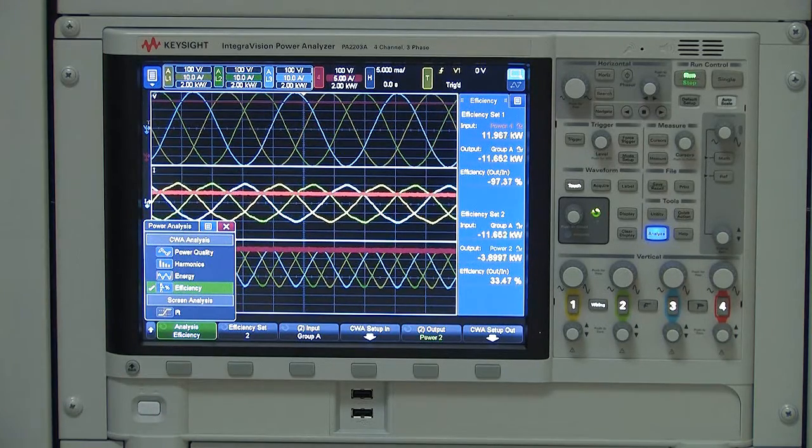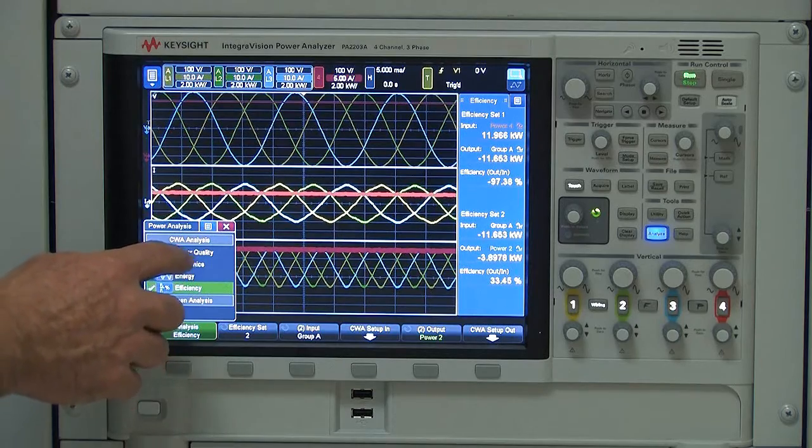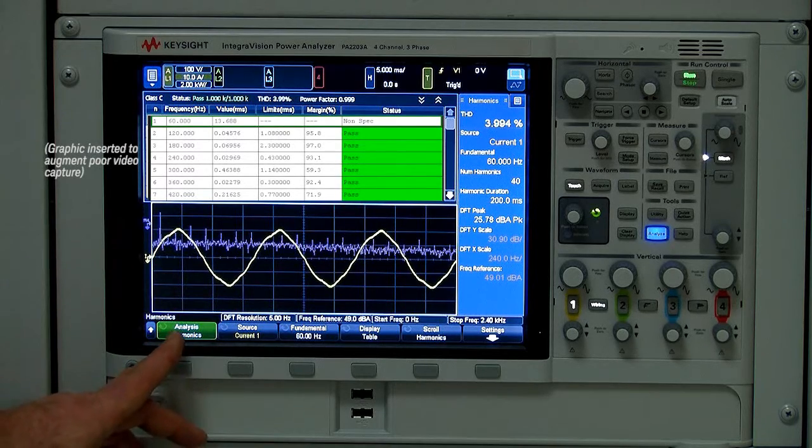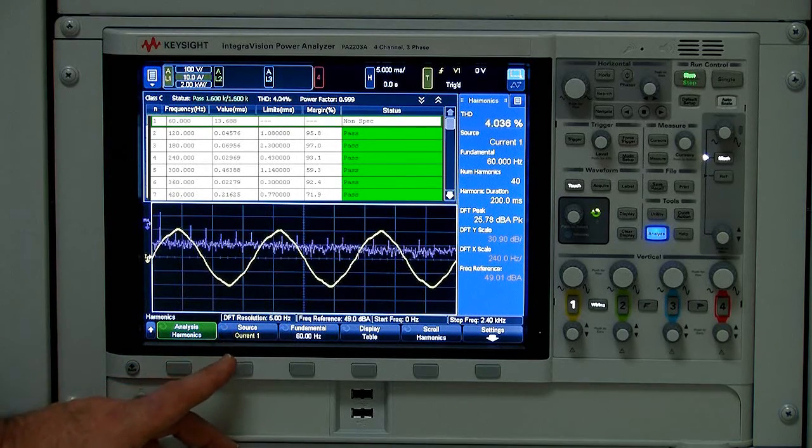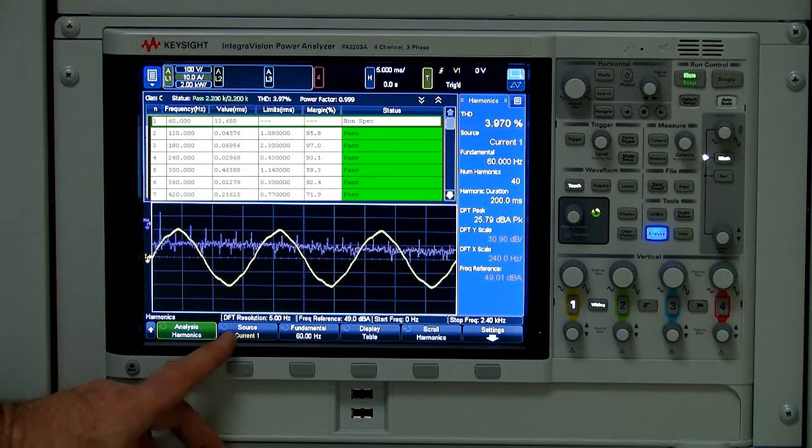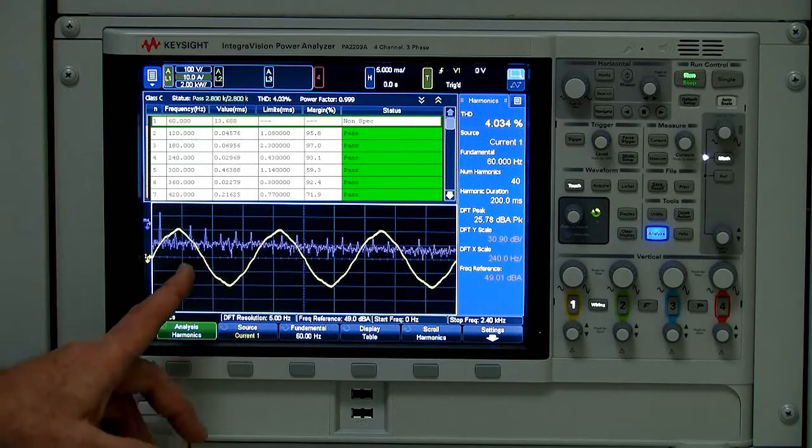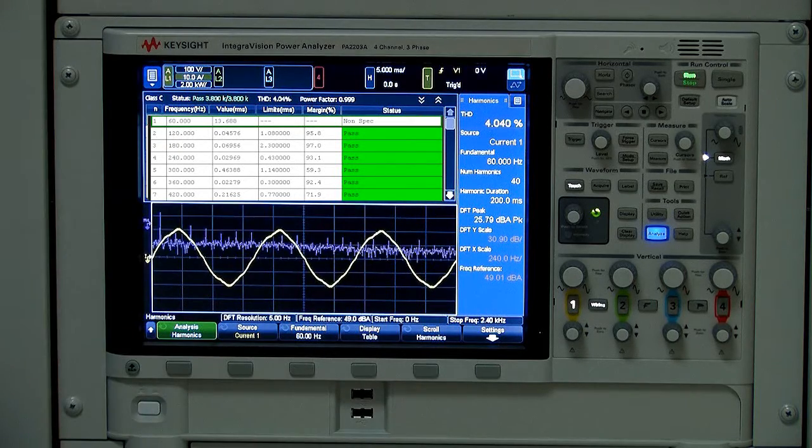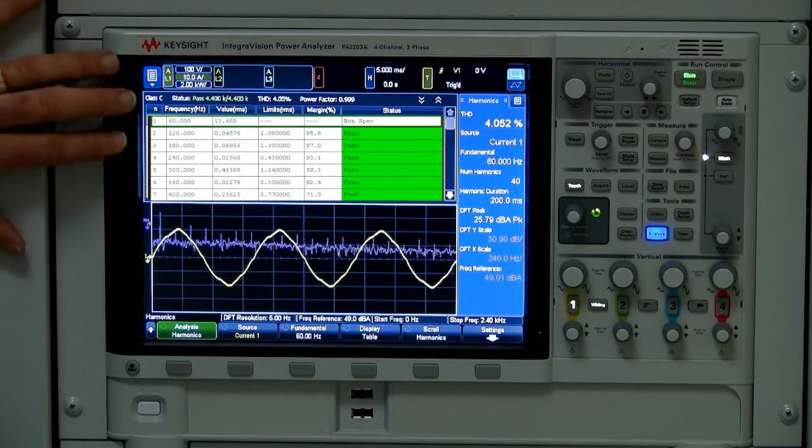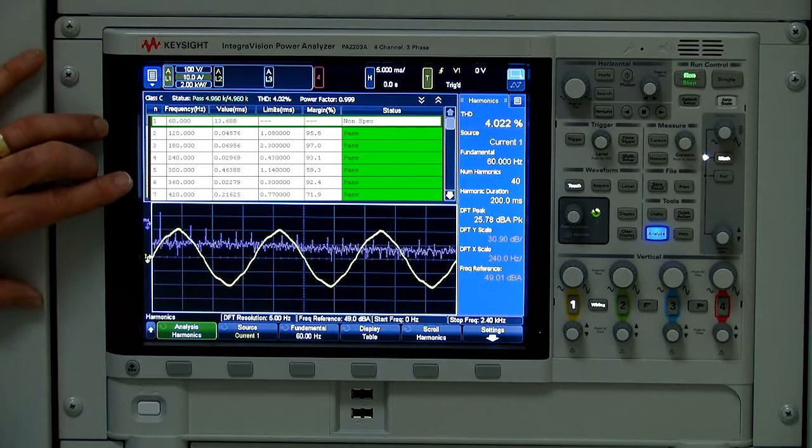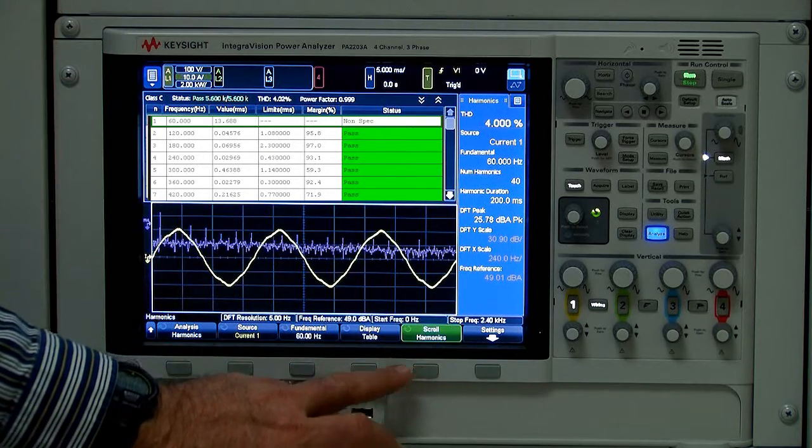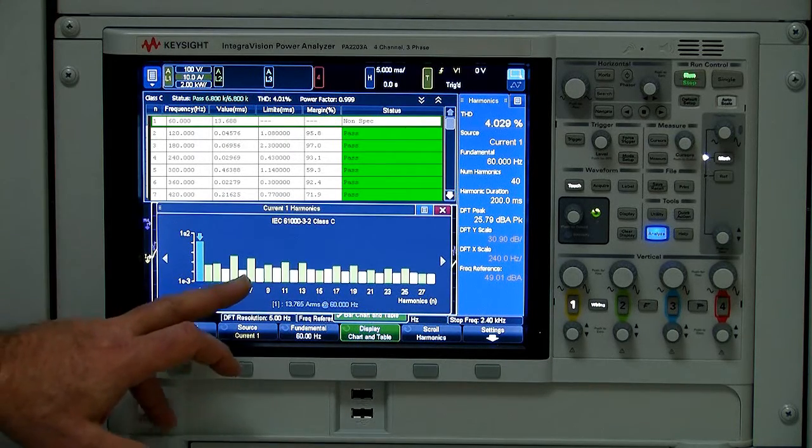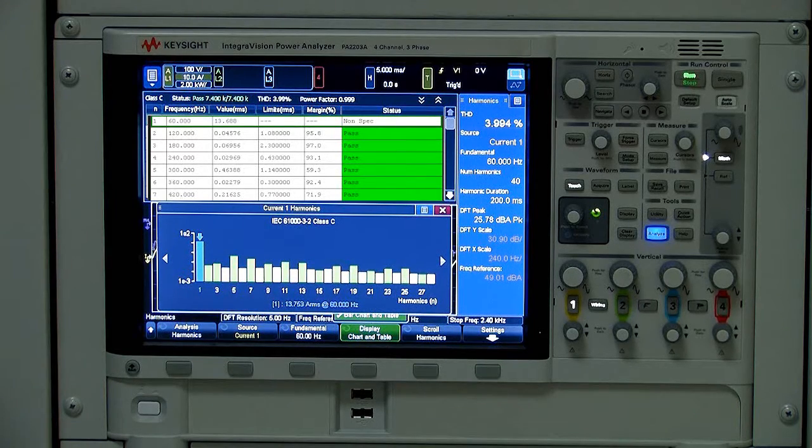Another test that you might want to look at would be to look at the harmonics of some of the signals. In this case, I'm looking at the harmonics of one of the phase currents, phase current one, which has a total harmonic distortion of about 4%. And each one of the harmonics of that are showed here. You can also display that in a table format and see the various sizes of each of the harmonics there.